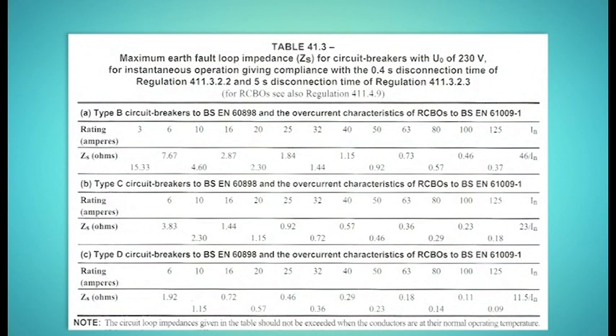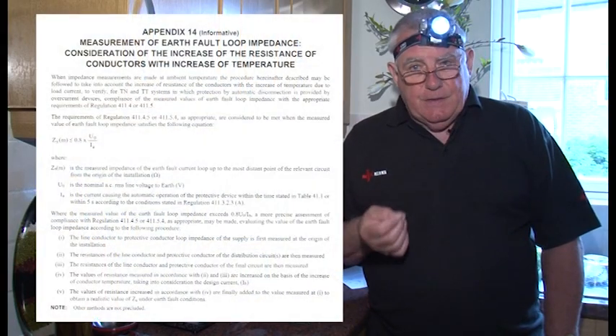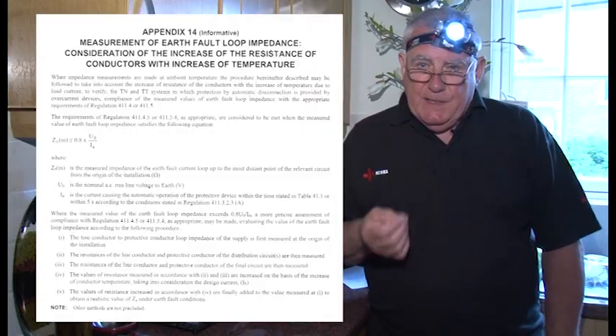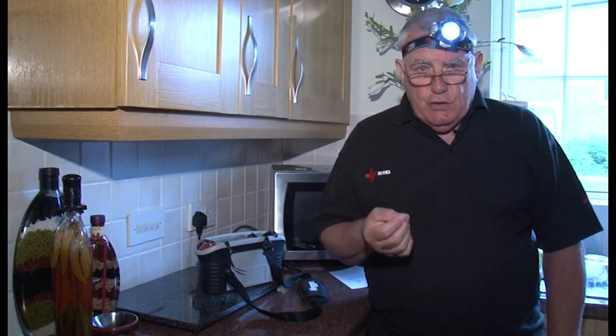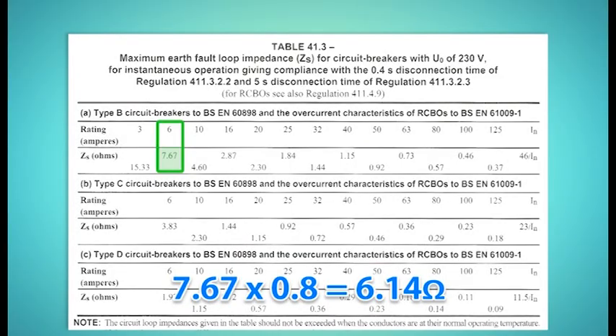Now looking at table 41.3, we can see that the maximum ZS for the 6 amp type B circuit breaker to operate is 7.67 ohms. Now our ZS is well below this, but it's important to remember that the regulations do require an adjustment to the figure to allow for the increase of the resistance of conductors with increase of temperature when a circuit is under load. You can find guidance on this in Appendix 14, but I always call it the 80% rule of thumb method. So basically the tabulated ZS needs to be reduced to 80% of its value. You can do this just by multiplying by 0.8.